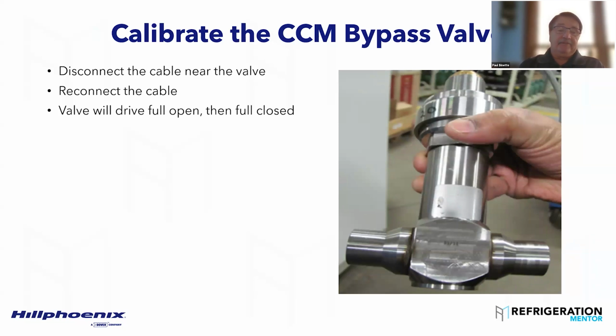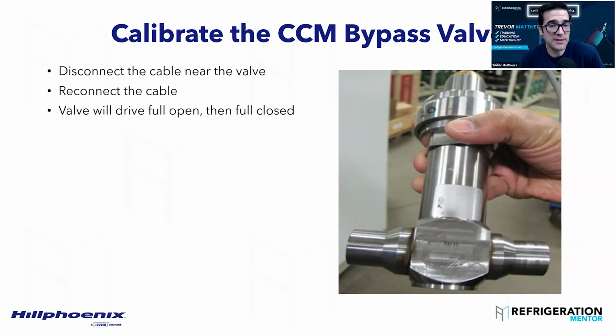So you can disconnect the cable. If you have an old 326A, you can power cycle the 326A. That'll calibrate your HPV and your bypass valve. With Copeland's the same way. You just, on the XM controller, the bottom right, you pull off the big clip on the bottom right, repower the valve, power cycle it. It will calibrate the valves. Perfect. And it's important to do that.